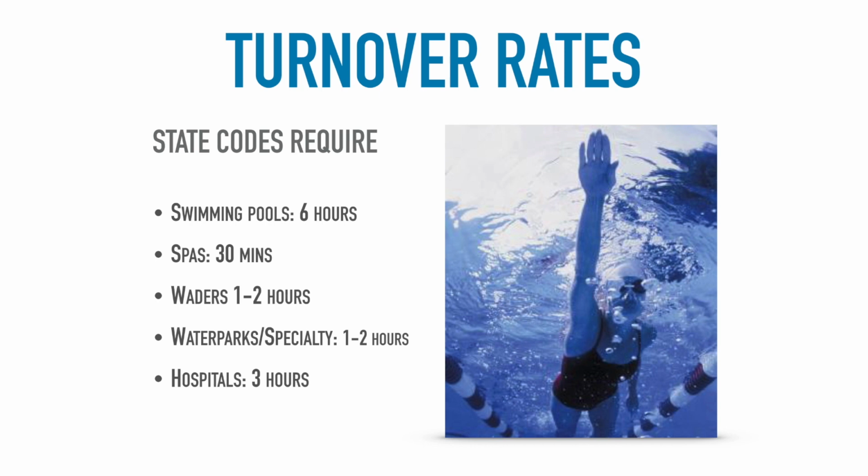Now, for those of you out there who may be working on wader pools, baby pools, or kiddie pools, they're all kind of the same thing. They just have different names. You're going to be at a 1 hour turnover rate on that. Anybody who has splash pads or specialty parks or water parks, you're going to be at a 1 hour turnover rate on those as well. Anybody who is working on a therapy pool is going to be at a 3 hour turnover.